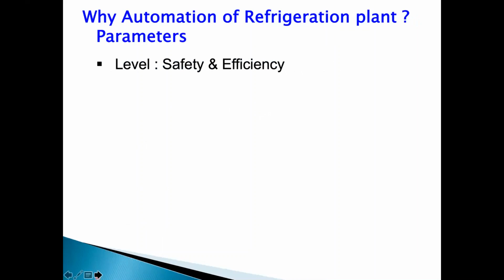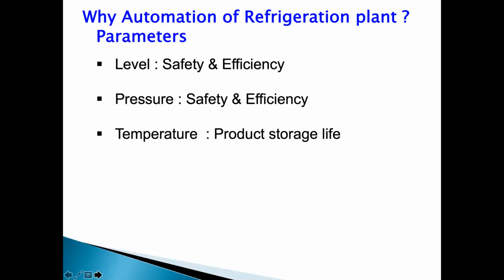So when we say automation, which are the things that need to be automated in an ammonia refrigerant plant? One is the liquid level, and we'll see some of the reasons why we need to control liquid level. As we all know, heat transfer takes place from liquid to vapor phase in an evaporator, depending on the liquid level. The systems are all pressure and temperature dependent, so we need to maintain constant pressures. Of course, when you are storing or processing a product, we need to maintain the temperature. That is the main objective of the refrigerant plant. We need to maintain temperature below ambient, and that's the reason we have refrigerant plants.